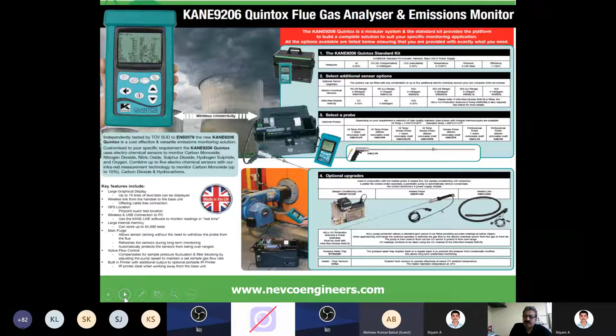So these additional options you can have: an extra heated sample line, extra length of the probe. The probe length, this shaft, can be small, half meter, 1 meter, or 1.5 meter. We can have custom-made up to 2 meters, 2.5 meters also for the device. Recently we supplied to a power plant in Karnataka. They wanted the sampling probe to be 2.5 meter, but it is difficult to carry, because the chimney is very big, with a diameter of 6 to 7 meters. So they wanted minimum 2.5 meters.